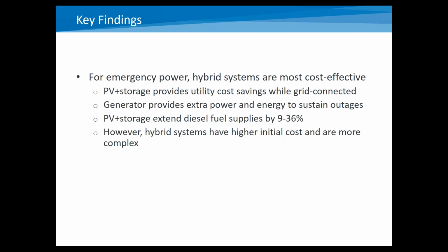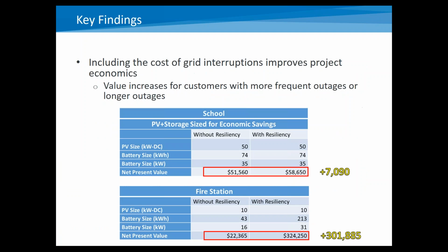Another key finding, as Kate mentioned, she already touched on this, so I'm not going to spend too much time, but hybrid systems tend to be the most cost-effective emergency power solution, and that's when resiliency is really your primary driver. This key finding, I think, is fairly straightforward common sense. We found that when you include the cost of grid interruptions, in other words, including a value of resiliency, this really improves the project economics. And as Lars already highlighted, that benefit is much larger when you're looking at a site on a radial grid where outages are more frequent versus a network grid where you don't experience as many outages.